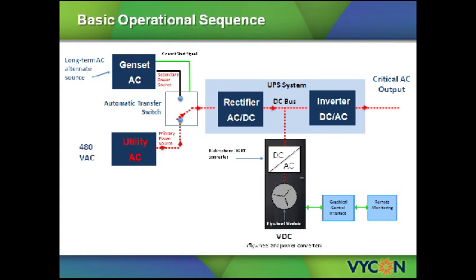During normal operation, when utility power is available, the VDC will take energy from the DC bus of the UPS and use this to motor or spin the flywheel to its normal operating speed of 37,000 RPM, converting electrical energy into stored kinetic energy. At 37,000 RPM, the flywheel is considered to be fully charged and reduces the amount of energy being consumed from the DC bus of the UPS. The flywheel will continue to maintain this speed while the utility power is present.